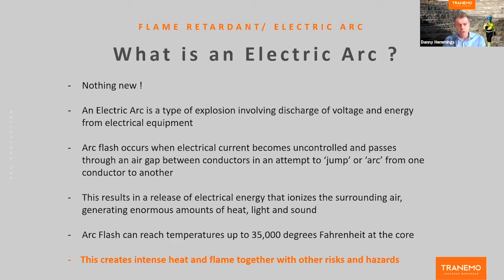it jumps or arcs across. And in that process, there's a huge release of electrical energy that ionizes, and that creates large amounts of heat, light, sound, and pressure. Extremely high temperatures are achieved at the core of the arc, but in milliseconds. So it's a big bang, big flash, and then it's kind of gone. And then the risk hazard associated with it very often is the cumulative effects post-arc flash.